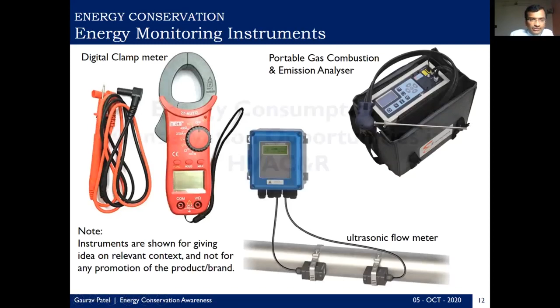Anemometer, you can find the velocity of the air. This is the temperature and RH sensor, mostly required for HVAC&R engineers. This is the clamp meter. Based on that, you can find the different amperes and electrical measurements. This is the ultrasonic flow meter. Based on that, you can find the flow rate in the pipes. And this is the combustion and emission analyzer for gas-based combustion processes. Now I will talk about the HVAC&R appliances, what the possibilities can be in this domain.